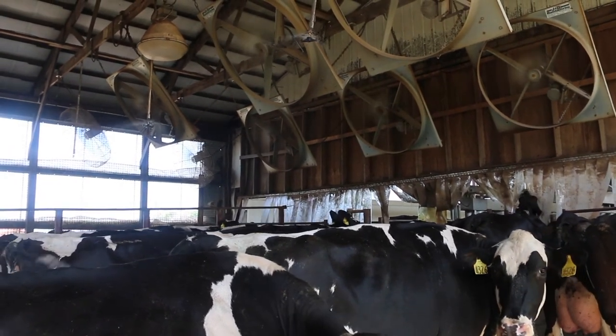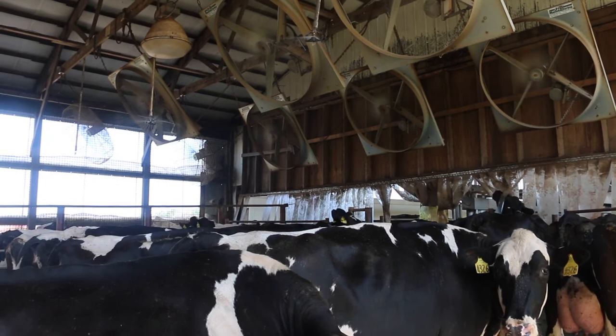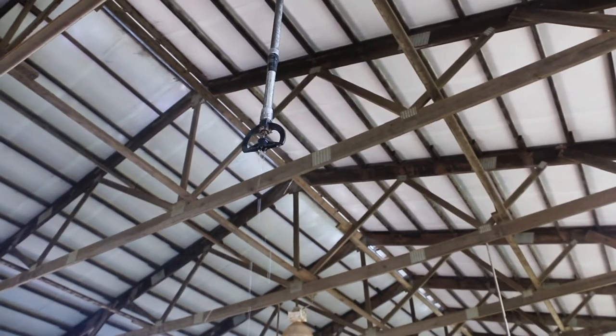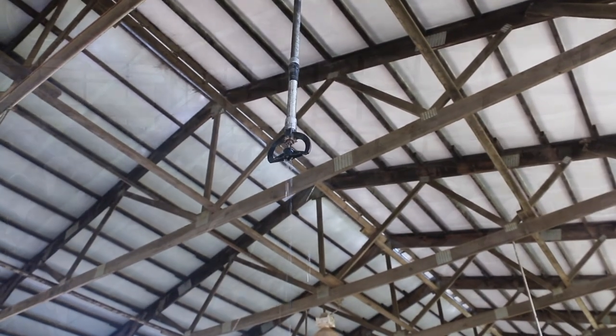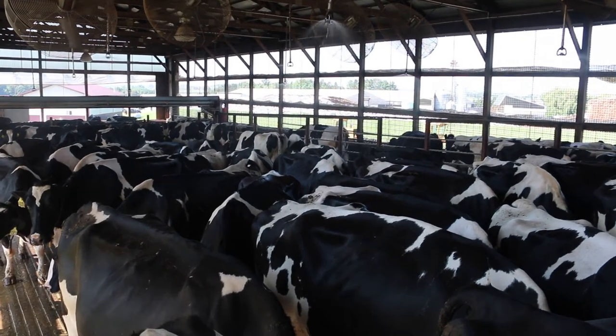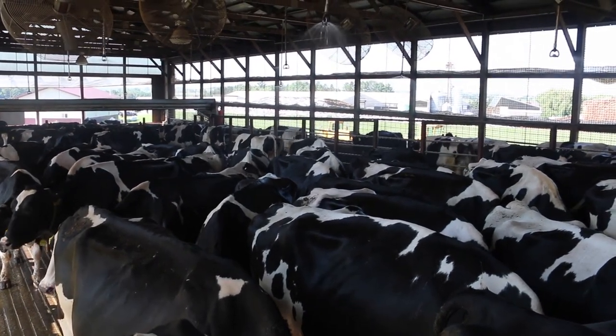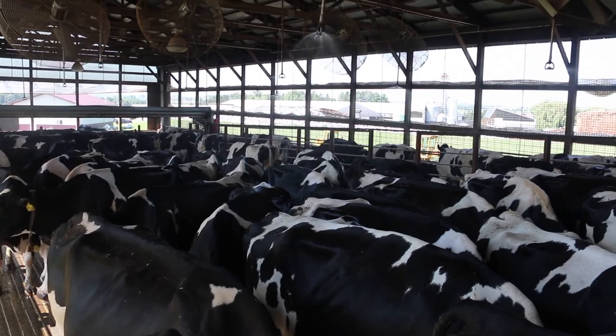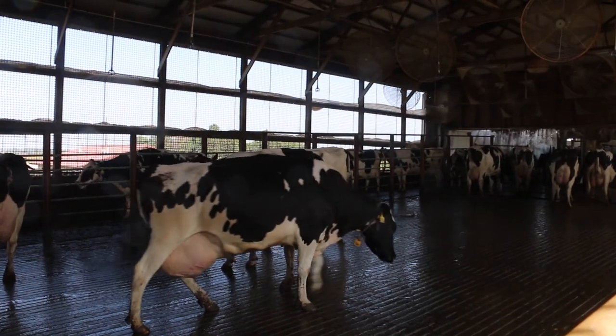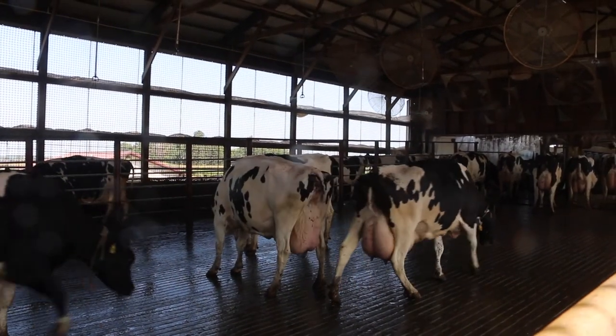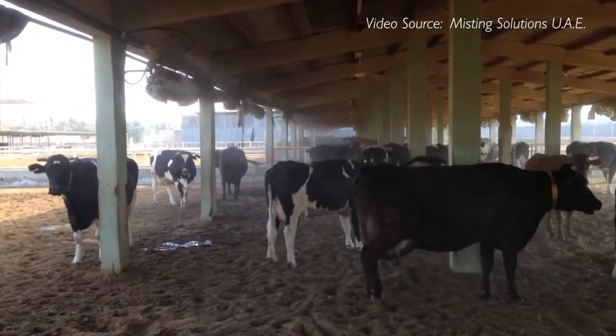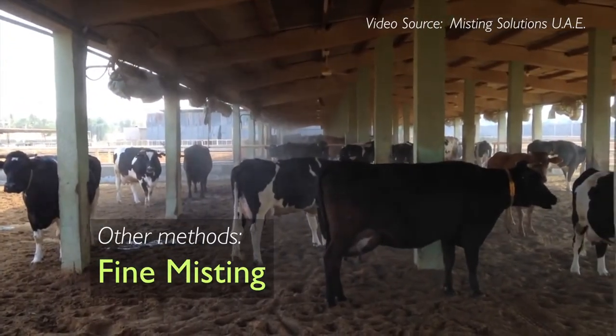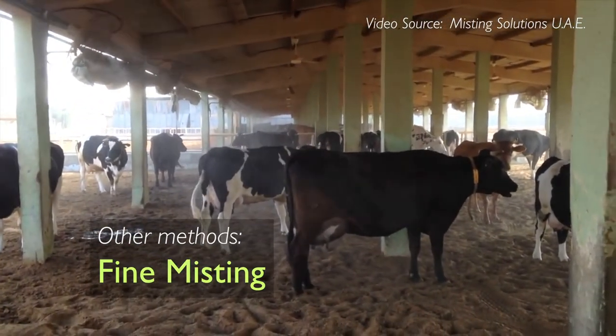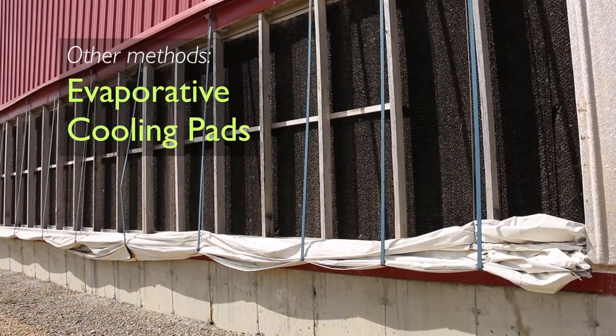Sprinklers can be set up on a timer to go on and off in intervals. The dry intervals should allow enough time for evaporation to occur before the next sprinkling interval starts again. This saves water and enhances evaporative cooling. These intervals can be set to change with the ambient temperatures. Other methods to increase evaporative cooling include fine misting systems or evaporative cooling pads.